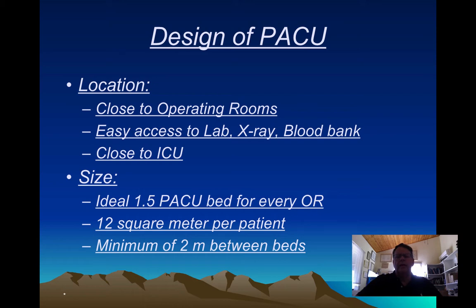1.5 beds per OR. In Aruba, we have 5 ORs, so it would be advantageous to have between 7 and 8 PACU beds. It is recommended to have about 12 square meters per patient, and the distance between patients from bed to bed should be about 1.5 to 2 meters. This is of course ideal. We're not always able to apply these requirements, but in Aruba we're doing very close to what is recommended here.